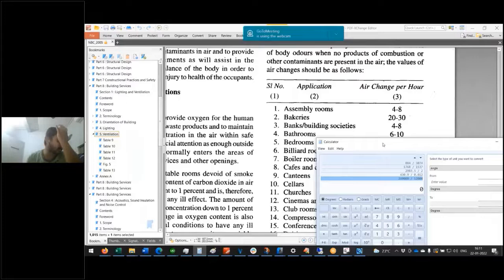Oh, not... okay, 10 meters. Room volume I have to take. Okay, so 3 into 10 into 10, so 300 cubic meter is my volume, right? So that 300 cubic meter, if I want to change it 8 times, I have 2400 cubic meter that I have to ensure gets out every hour.